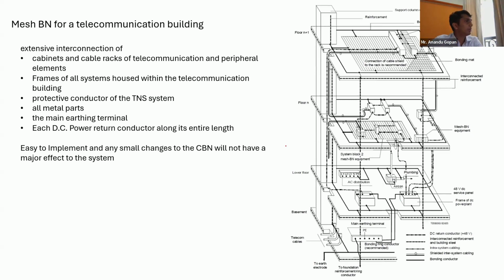So when it is going to be a mesh bonding system, again I repeat, you have to connect your cabinets and cable racks to the system. It must be a TN-S system, and the protective earth must be connected. All dead metallic parts you are supposed to interconnect, preferably to the MET, and when you interconnect all the METs together, you will form a CBN, and the DC power return path along the conductor, you are supposed to earth it.